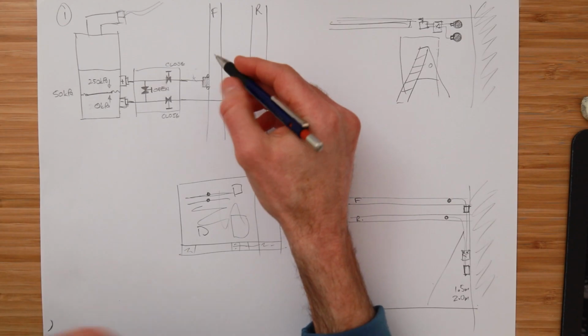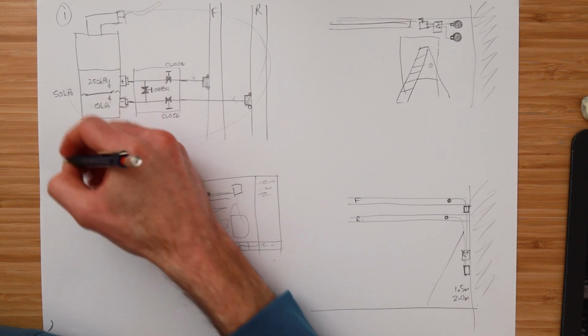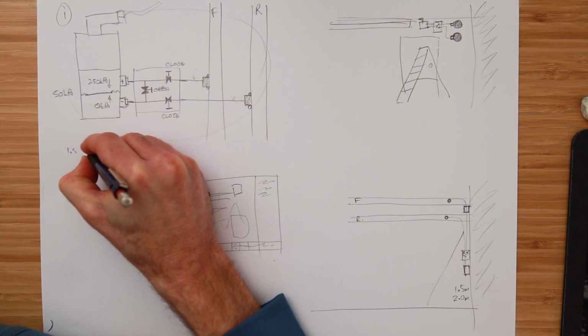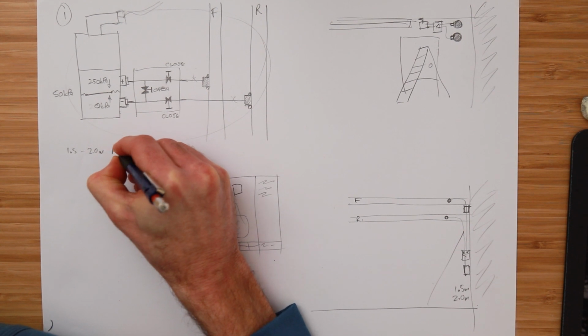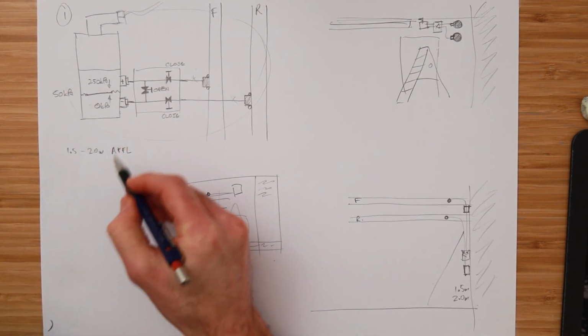So I think in last week's video, we spoke about this idea about having this installation little check sheet or cheat sheet or little specification that you would issue to your electrical subcontractor that explains all the requirements for your company's rules around installation. You could create the exact same little sheet to give the mechanical contractors for the installation of the system pressure transmitter, how that works. So maybe you would draw this on this little check sheet for mechanical. Maybe you would say here on the sheet, it should be installed at 1.5 meters to 2 meters above finished floor level. Maybe you tell them that on the sheet.